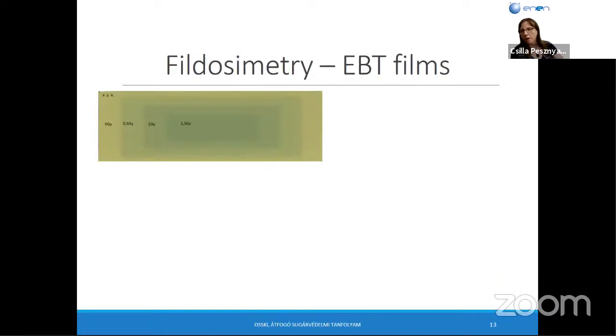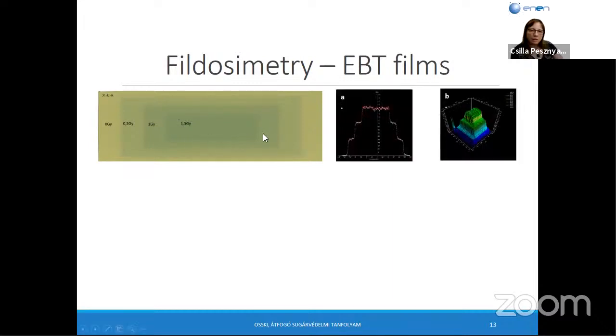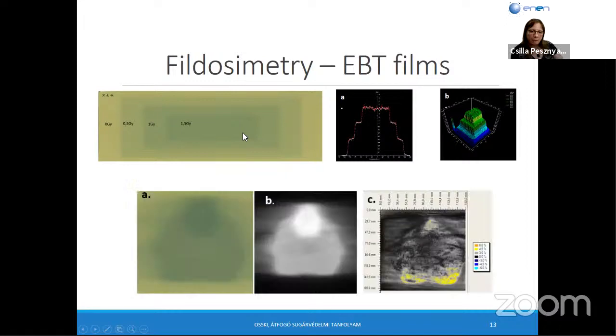Then we also use film dosimetry. It is a monomer, and after the irradiation it can be polymerized. We can irradiate with different field sizes and different doses. With a special software we can see the shape of the beam in 2 and 3 dimensions. We also use it for verification of the treatment plans received from the treatment planning system. Here is the irradiated film, and this is the fluence of the beam from the treatment planning system. Here you can see the differences when we compared them.